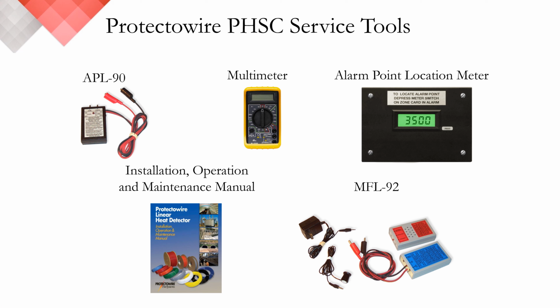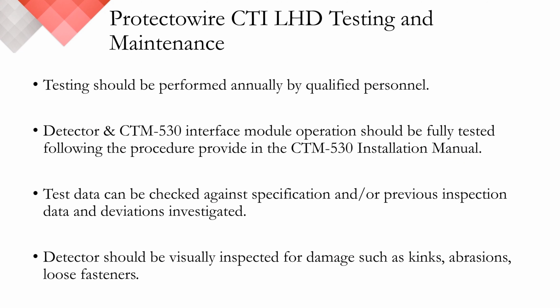Along with the array of installation accessories available, we also provide a number of tools to aid in the testing and servicing of your linear heat installation. Testing of the CTI detector follows many of the same guidelines for Class A and Class B circuit monitoring. However, with CTI detectors, we're able to take the test procedure one step further and actually perform a heat test without damaging the detector. This is accomplished through the use of the required test probe.